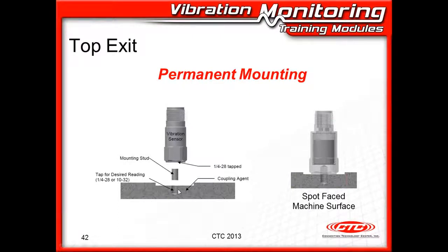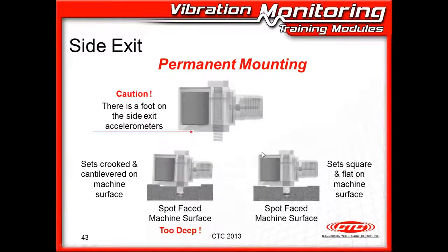Here's a good example of a top exit sensor. We have a nice spot face surface. We've got our drilled and tapped hole here. We've got our mounting stud, and we're going to bring that sensor right down and mount it onto our spot face surface. Don't be afraid. If you want to, you can put a little bit of Teflon lubricant or something under here. Anything you can do to take the air out of the micro cracks that are in the surface there, that would be a good thing to do, because we always transmit vibration through a solid better than we do through air.